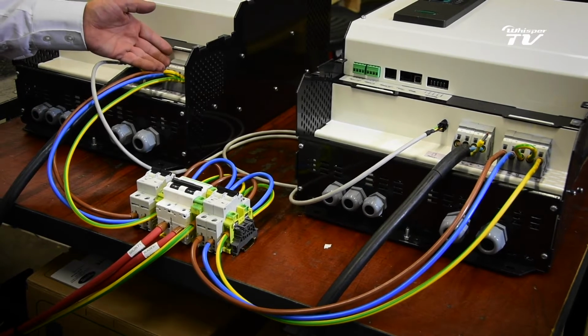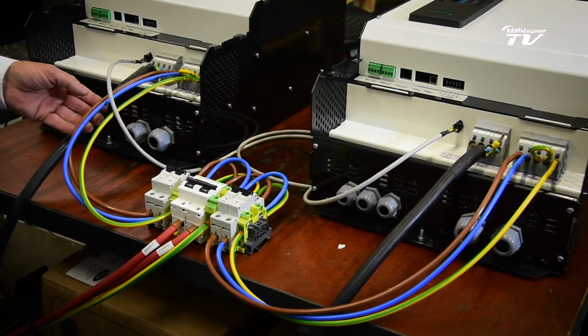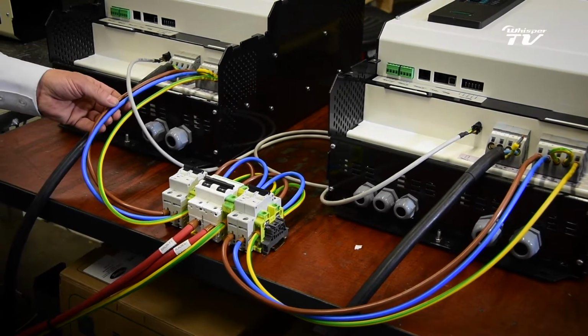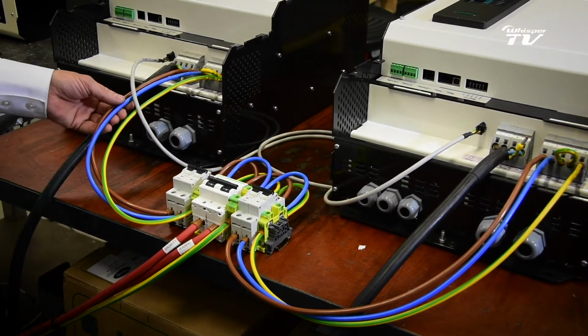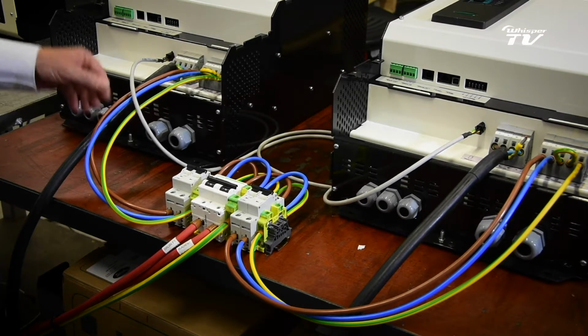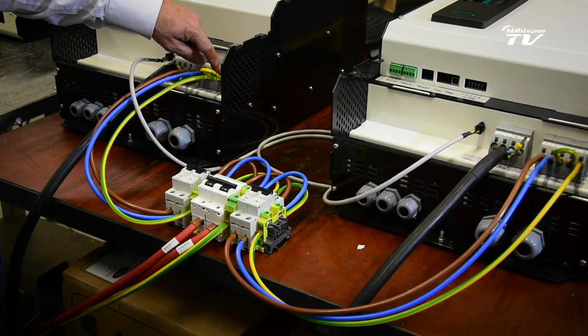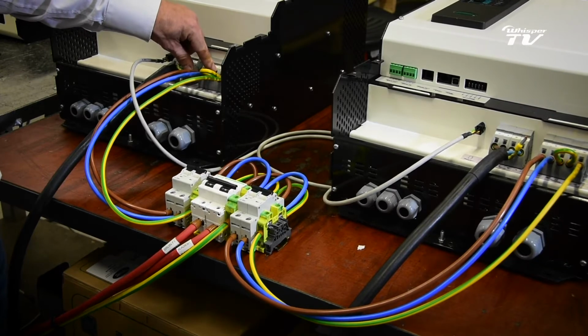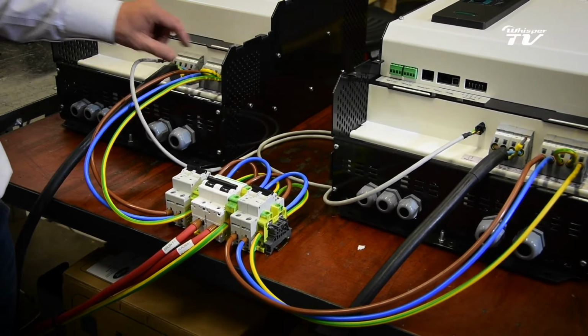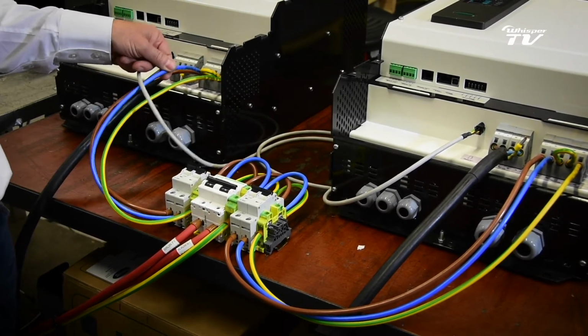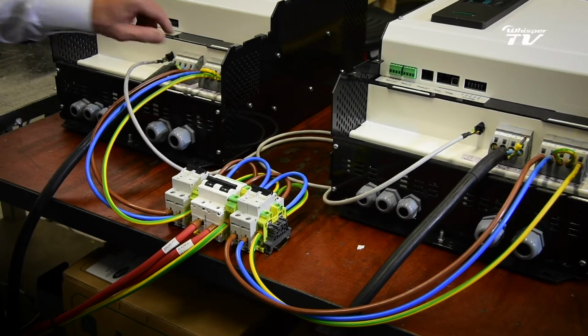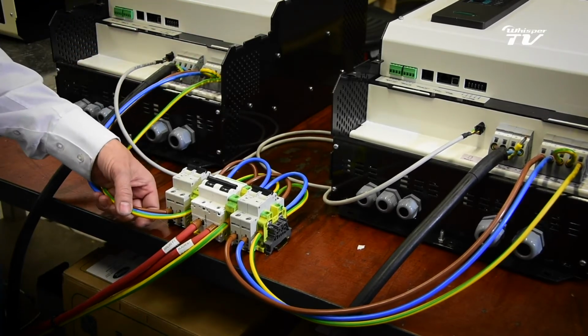On the side next to it we will see the output. Normally we have 230 volt or 120 volt output voltage, which is a floating system. In this case we have made a neutral ground connection, so we make it not a floating system anymore. So it's fixed line and neutral. Then we have the protective earth. That's connected to a 50 amp breaker.